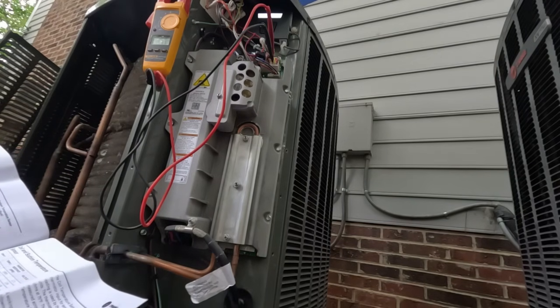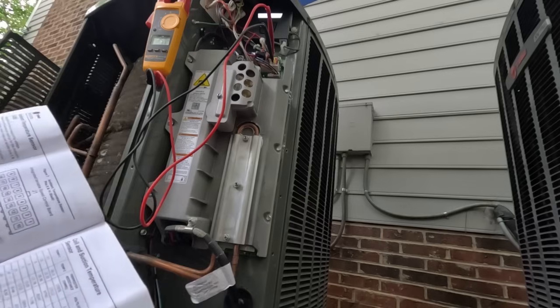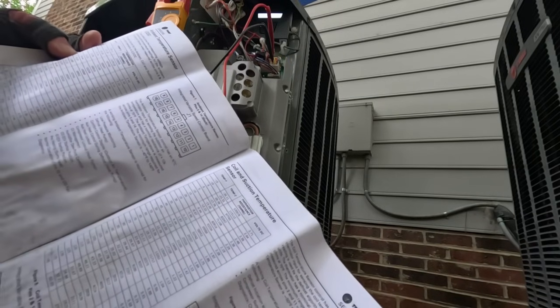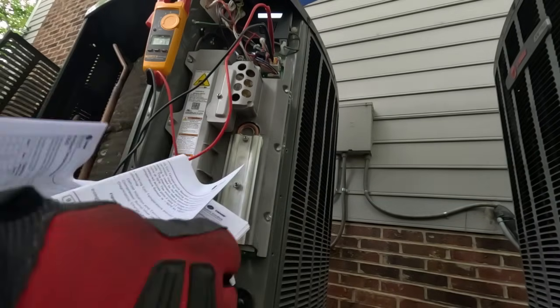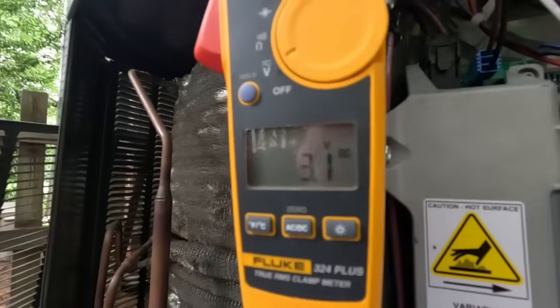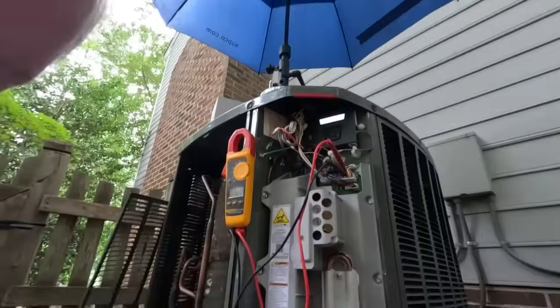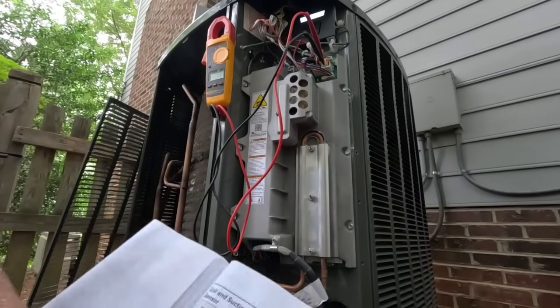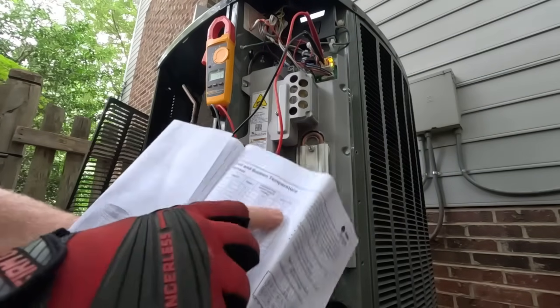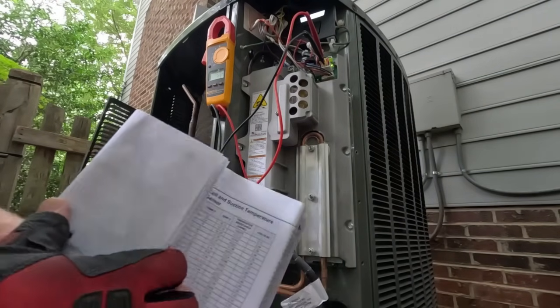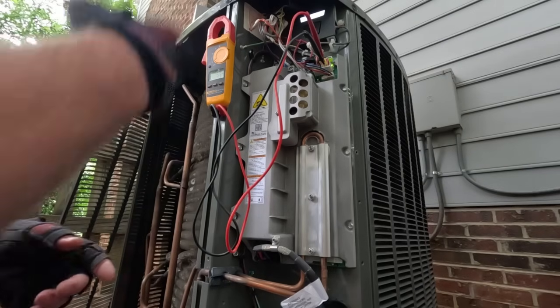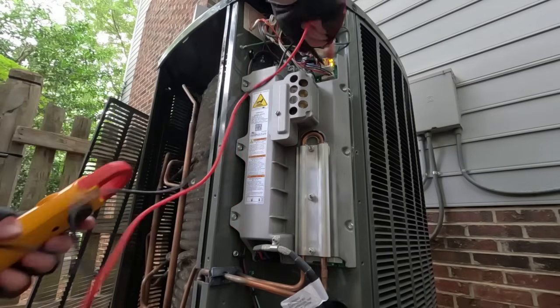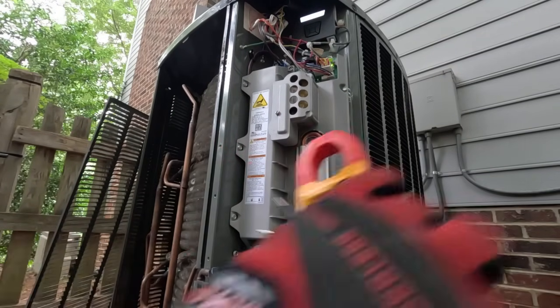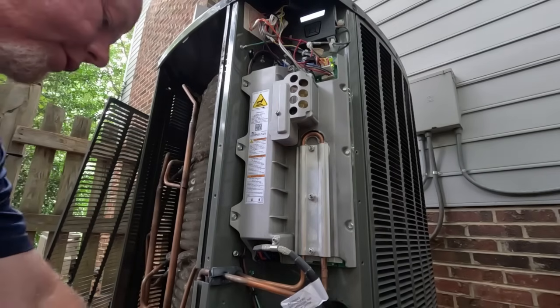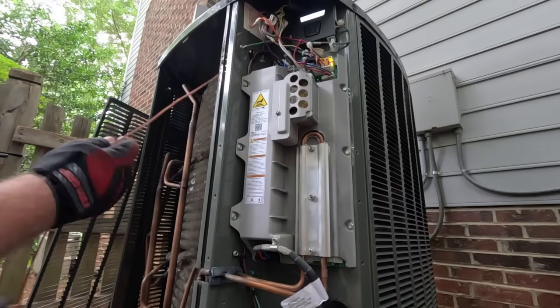Coil and suction line temperature sensor. So right there, we're getting 3.1 volts DC, and the chart stops at 2.7 right there, and that's minus 15 degrees. So this sensor, it is what it is. That's the most common problem with these units, these temperature sensors.